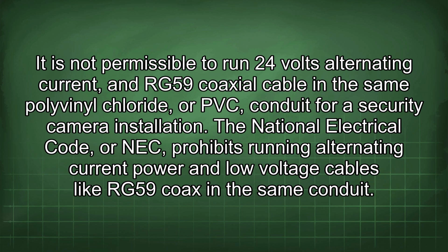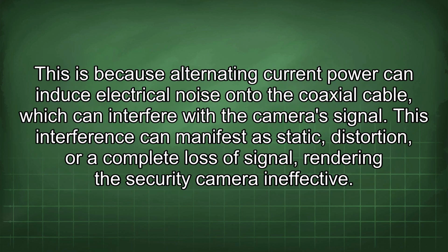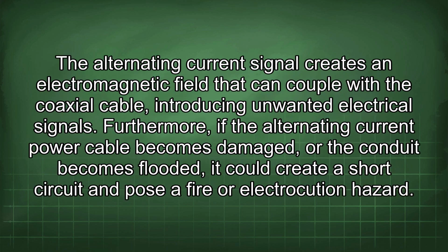same conduit. This is because alternating current power can induce electrical noise onto the coaxial cable, which can interfere with the camera's signal. This interference can manifest as static, distortion, or a complete loss of signal, rendering the security camera ineffective. The alternating current signal creates an electromagnetic field that can couple with the coaxial cable, introducing unwanted electrical signals.